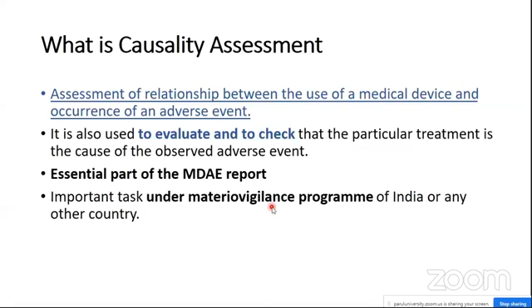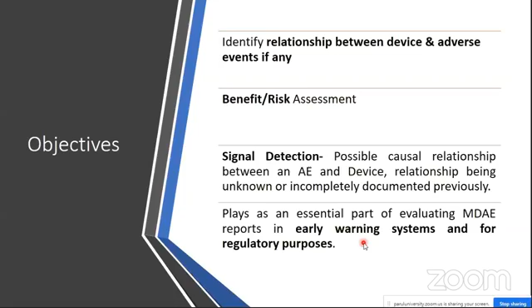Our specific objectives include identifying the relationship, as I said, between the device and adverse events. While doing this, we are in turn doing a benefit risk assessment also, because sometimes you know that the device is the reason for the adverse event, but if you compare it with the benefit that the patient gets, the benefits always outweigh the risk. That is what we do in risk management or in any causality assessment practice. So we need to consider that benefit risk assessment. It will also help you detect signals which may have been previously unrecognized. And as I said, it's an essential part of evaluating medical device adverse event reports in early warning systems and for other regulatory purposes.